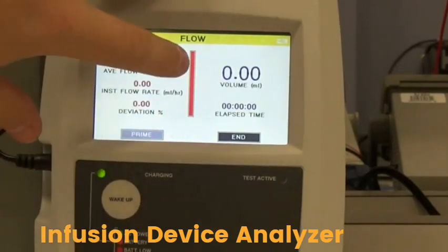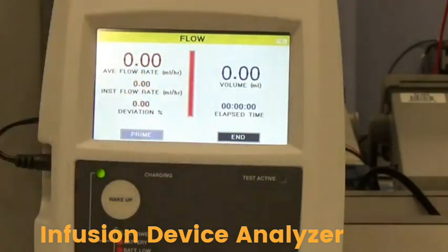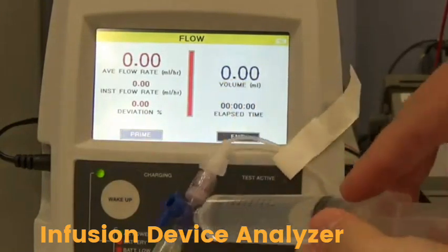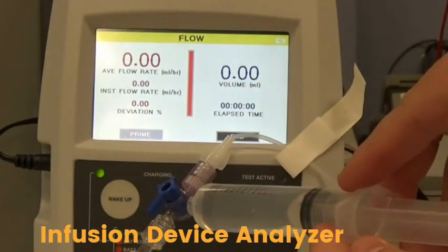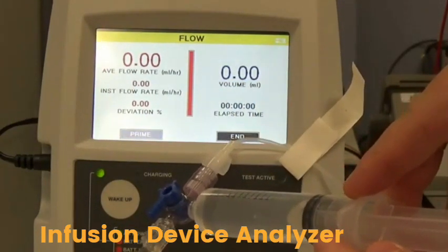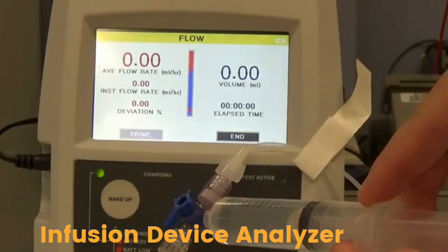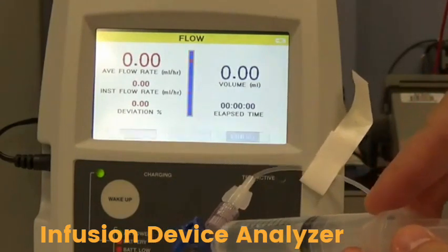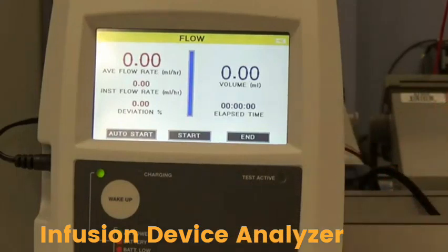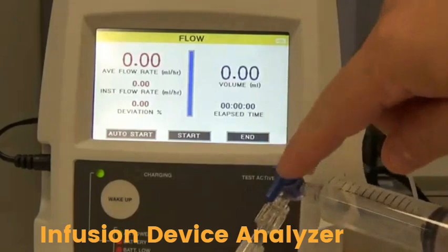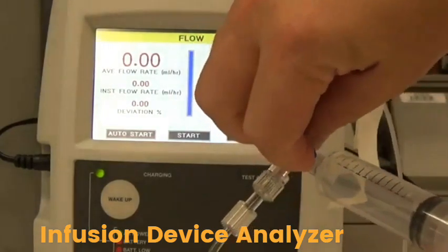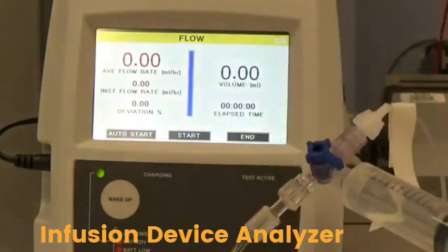And the most important thing here is notice the red bar. That tells you the device is not primed. This is where the syringe comes in. So as I press on the syringe, you'll notice that the red bar shows up as a blue bar. There it goes. And once it is completely blue, you're actually ready to go. Don't forget to change your switch to close the syringe and open your infusion device.